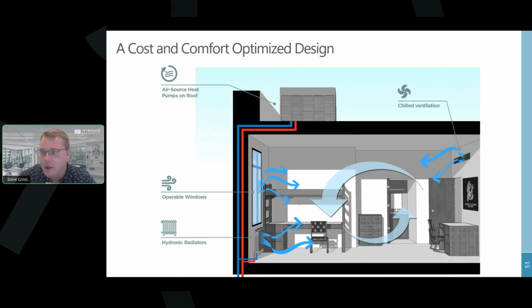So there is some level of macro approach here, it's not very granular. Every dormitory on the western or southern side is going to get the same temperature air out of the DOAS system. Very simple, very cost effective to just add a slightly larger mechanical cooling capacity to the ventilation system.